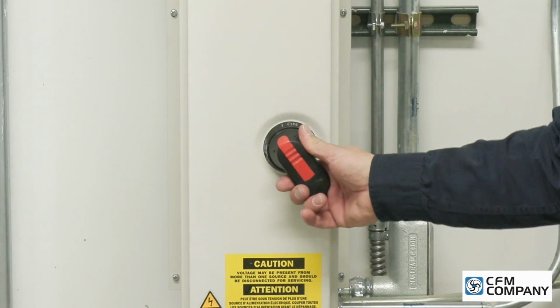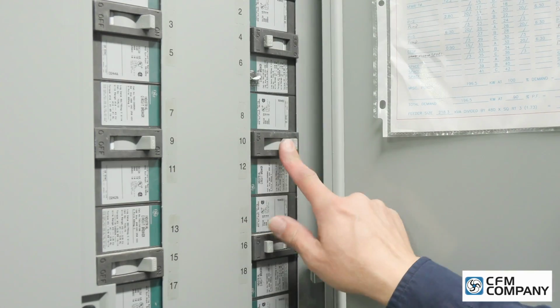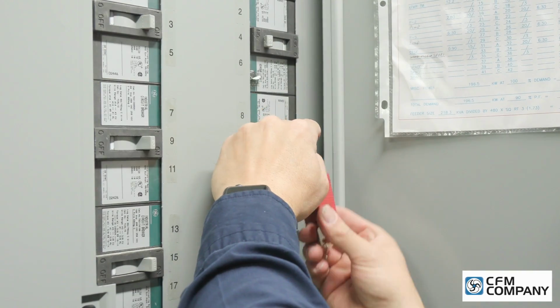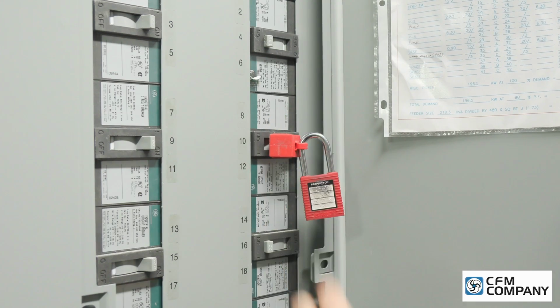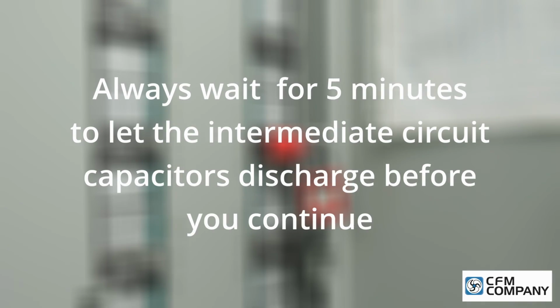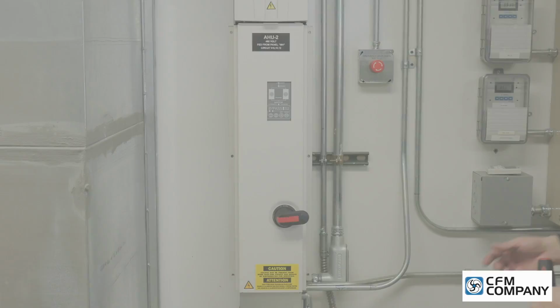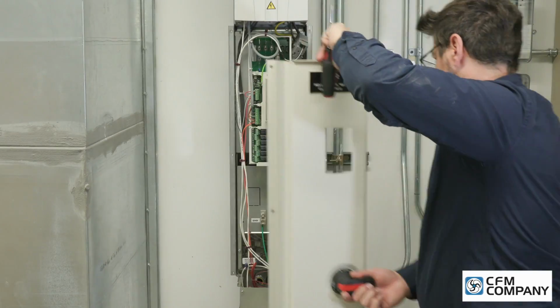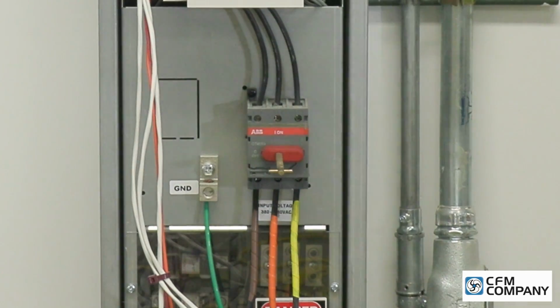Before removing the front cover of the drive enclosure, disconnect the power to the drive. Lock out and tag out the circuit disconnect and make sure that reconnection is not possible. Always wait for 5 minutes to let the intermediate circuit capacitors discharge before you continue. Remove the front cover of the drive. Verify that there is no voltage on the line side wires by using a voltmeter.